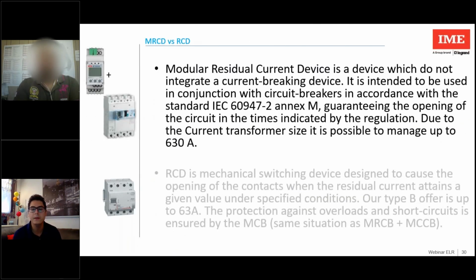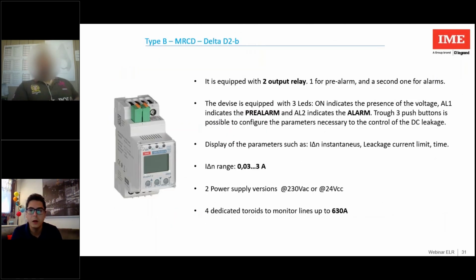In this slide, we find the difference between a classic RCD with the integrated breaker and our MRCD, able to work with all the breakers that guarantee compliance with the EN 60947 standard, such as disconnection within 40 milliseconds. This type B is equipped with 2 output relays, 1 pre-alarm and 1 alarm, and a display capable of showing the instantaneous current values, the set threshold, and the intervention delay. For this series, there are 4 dedicated toroids to monitor the line up to 630 amps.